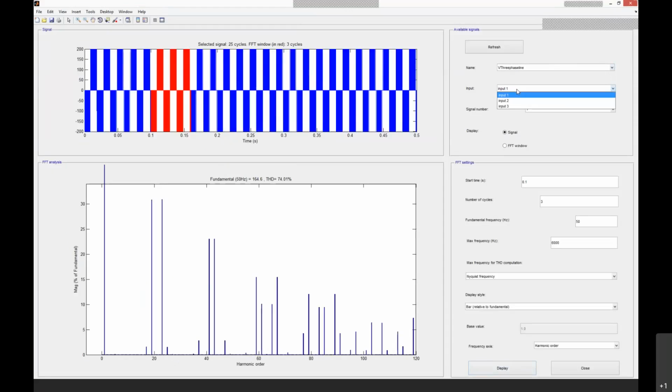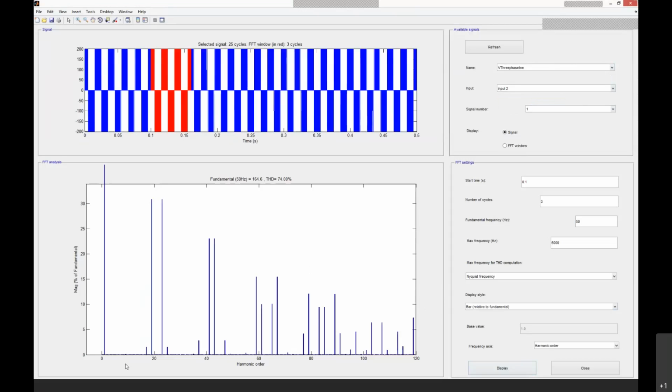So this is the input, that is A phase, this is B phase, and this is C phase. In the harmonic spectrum, you can observe that at MF there are no harmonics. Only the side bands of MF have harmonics. Here we consider that MF is a multiple of 3, that is, divisible by 3. We consider 21, so it is a synchronous PWM. Normally for three phase, MF should be odd and divisible by 3 if you want a synchronous PWM.